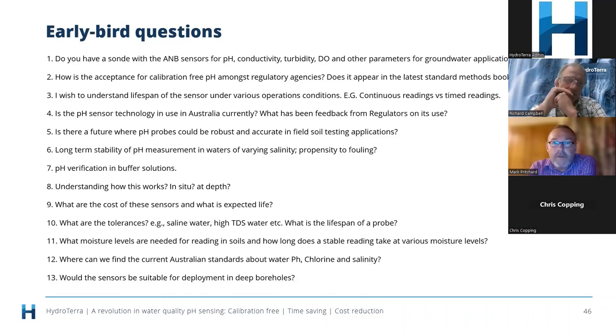It's the strength of the buffer solution that prevents us operating in that manner. The way to verify it today is to take a glass sensor, calibrate it, check the pH, and check our pH, and you'll see they're very, very similar—but obviously that's not what we want. So we're looking at finding a way to operate in those buffer solutions, but it's completely alien to the way we're operating today.